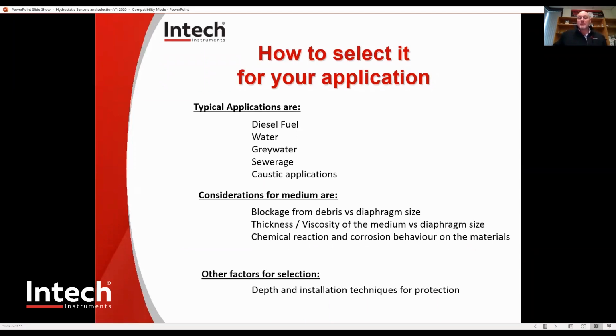Another thing to consider about your medium is blockage from debris versus the diaphragm size. The thickness and viscosity of the medium versus the diaphragm size. Obviously, the thicker, the bigger the diaphragm you need. If it's going to be prone to blockage and have large debris, then you might need to consider a large diaphragm also, but consider protection of that diaphragm. Also consider chemical reactions and corrosion behaviour on the diaphragm materials, and also the main body of the transducer.